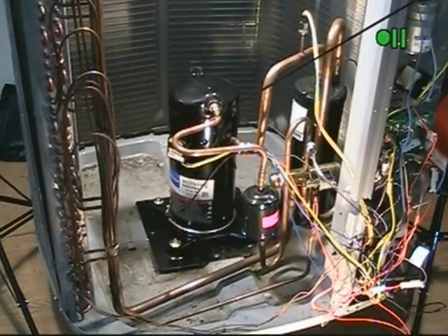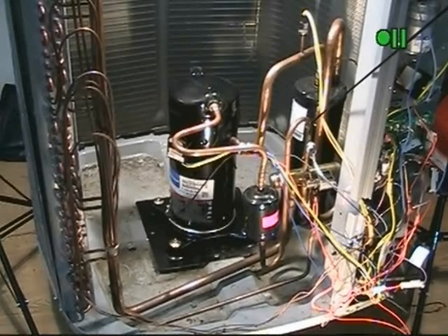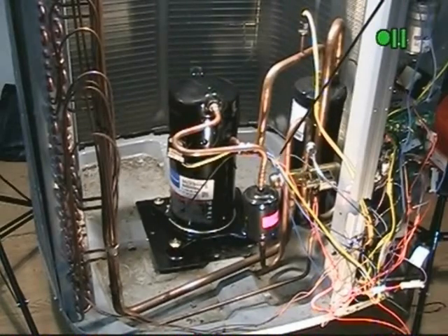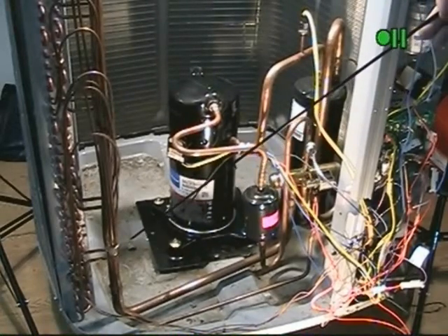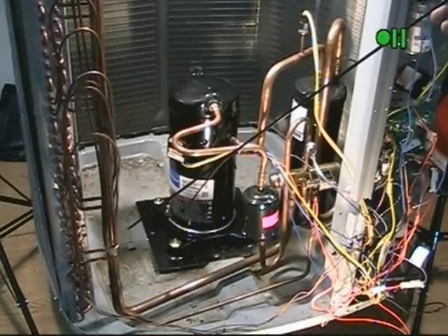Now this is a high efficiency heat pump that we've torn apart today to be able to view these components. In this particular unit, the high pressure, high temperature gas leaves the compressor, goes through a discharge muffler, then is channeled into the four-way reversing valve. During the AC mode, this refrigerant would go through the reversing valve and then be channeled through to the piping header of the condensing coil. And this AC mode will be the outdoor coil.